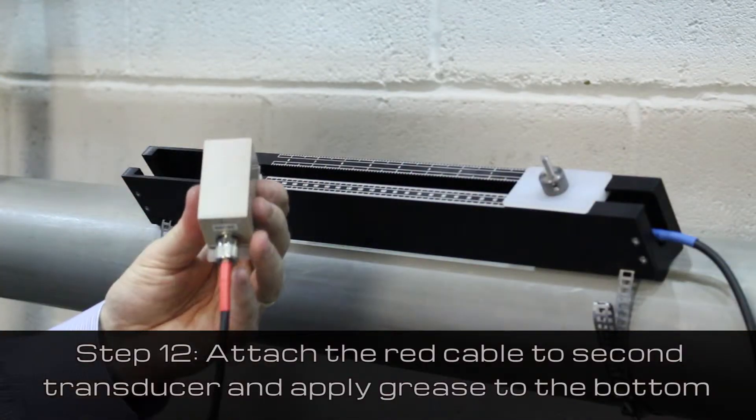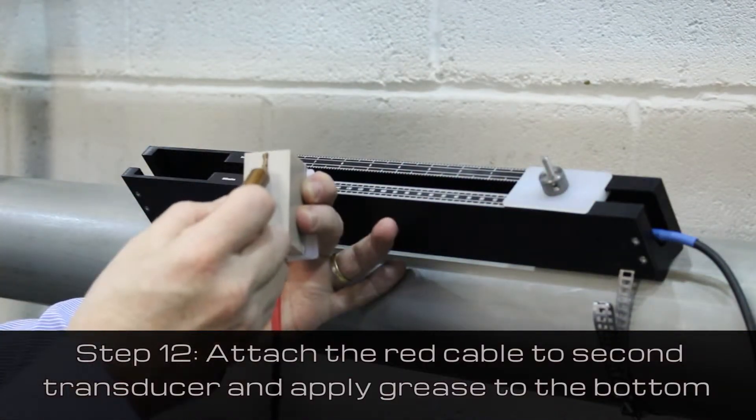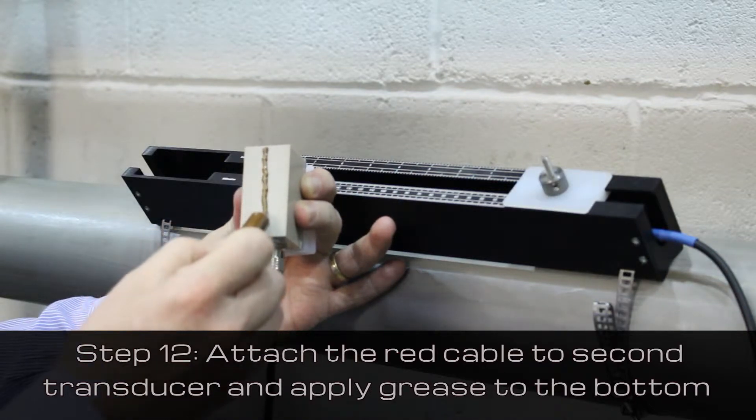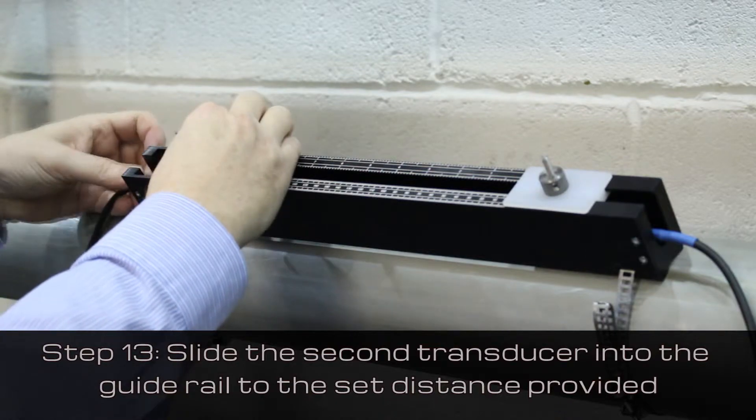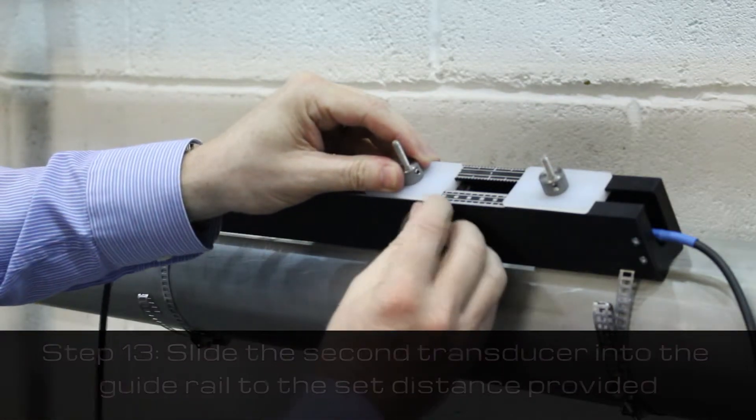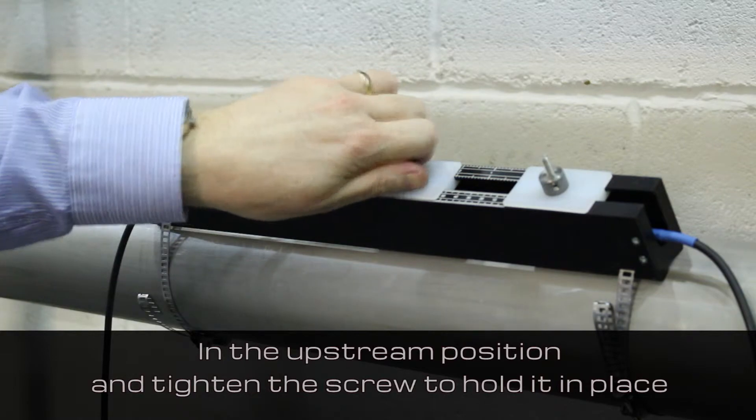Attach the red cable to the second transducer. Apply the grease and slide the transducer into the guide rail to the set distance provided by the flow meter in the upstream position and tighten the screw.